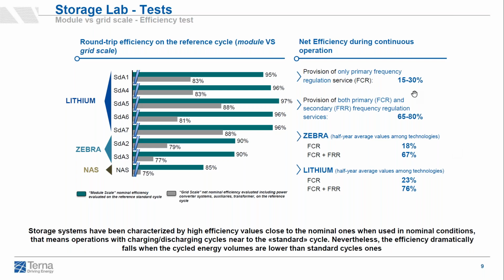So this is because primary frequency response, as we already said, requires a high number of power inversions, but has a low energy content in this kind of cycle. So if you consider that the losses of the auxiliaries could be considered more or less constant, obviously if the energy exchange is low, also the efficiency is very low. So it's better to operate the batteries in conditions, let's say, similar to the energy exchange that we have in a standard cycle, and this could be done also by combining different grid services.